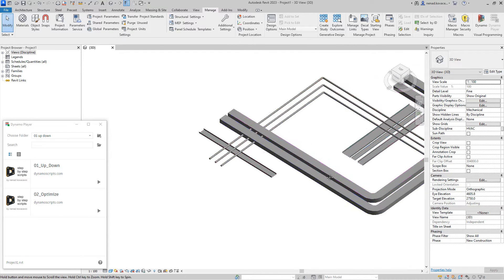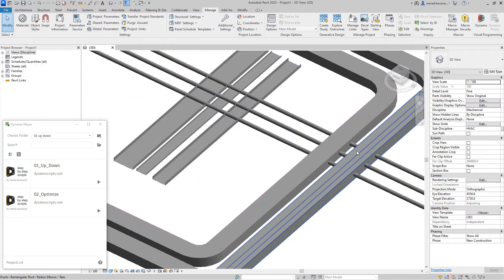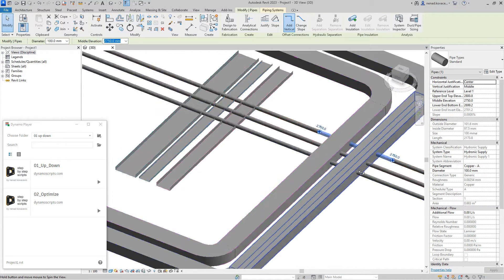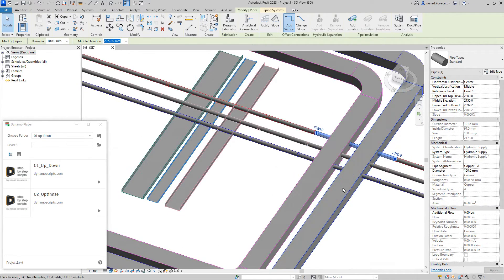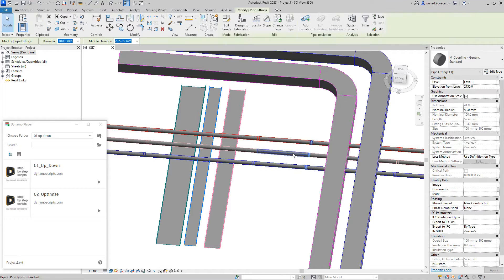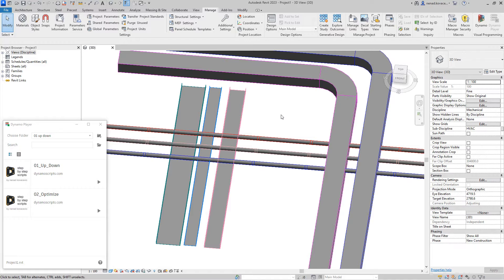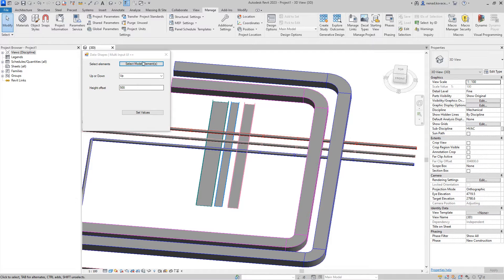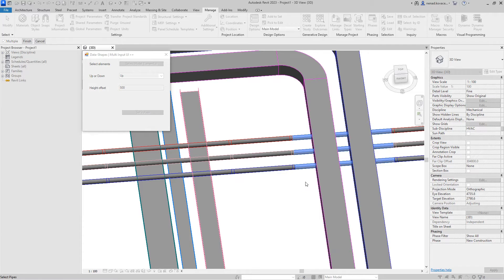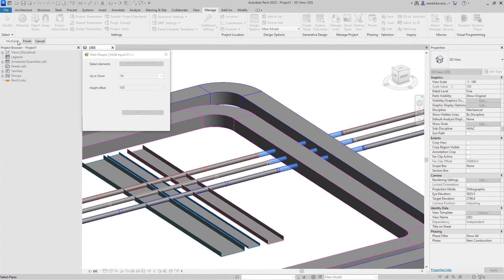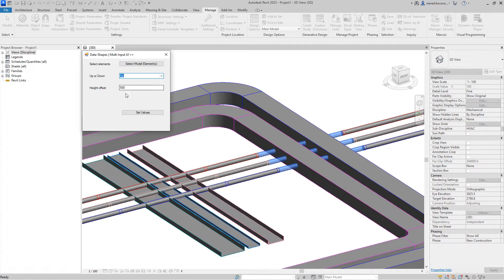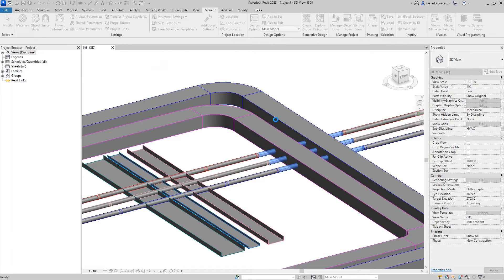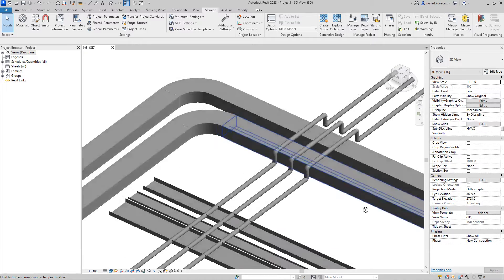Okay, over here I have some examples. Like in real life, when you want to move and create some movement of the pipes, cable trays, or ducts, you would need to split those installations first. So I did place unions over here with split command, and after that I can run the script. If we run the script, we have a simple user interface. Inside elements, we will select those three pipes over here and click finish. We need to say if we want to go up or down. Let's say that we want to go up. I'm in the metric system, so that's 300 millimeters. And now we moved those pipes up.